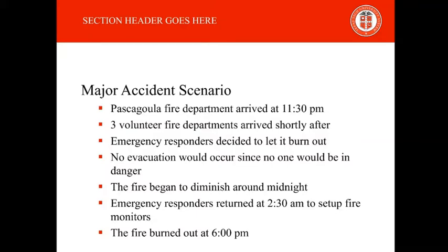The explosion and fire caused Enterprise to incur $17.5 million of expenses, and the plant was shut down for 6 months. Now that we've gone over the events that occurred on June 27th, let's talk about the root cause of this accident: thermal fatigue in the brazed aluminum heat exchanger.